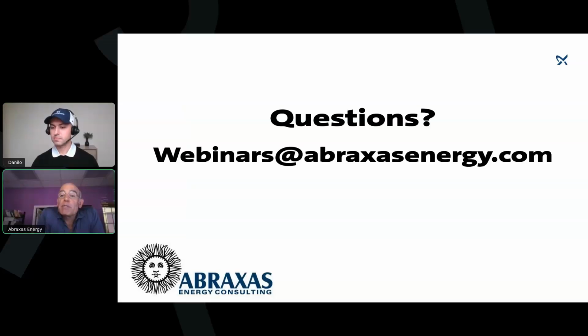What piping and pumping design do you recommend for VAV reheat designs while trying to minimize control and balance valve quantities? I think he's talking about distributed pumping, right? I mean, that's how you minimize valves and the valve authority problems, right? It's a distributed pumping system, but the question is, what piping and pumping design do you recommend for these distributed pumping? And I don't know the answer to that because it's really hard to come up with an answer without knowing the gallons per minute, the flow, the pressure you're overcoming, how many feet of head, right? Your pipe size is going to change based on that, and your pump as well is going to change based on that.